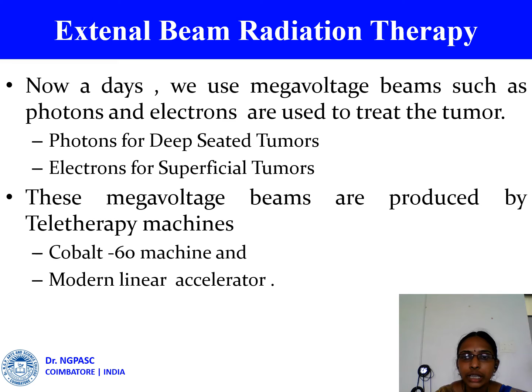A modern linear accelerator is a machine in which high frequency electromagnetic waves are used to accelerate electrons to a higher energy through a linear tube. This highly accelerated electron beam itself is used to treat superficial tumors, or it may be made to strike a target to produce X-rays for treating deep-seated tumors. Usually we use a 100 centimeter SSD in a LINAC.